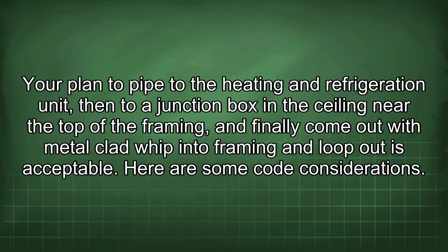Your plan to pipe to the heating and refrigeration unit, then to a junction box in the ceiling near the top of the framing, and finally come out with a metal-clad whip into framing and loop out is acceptable. Here are some code considerations.